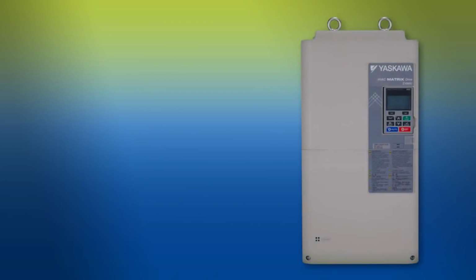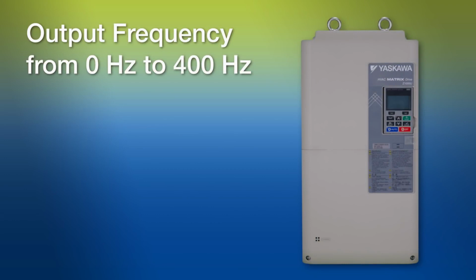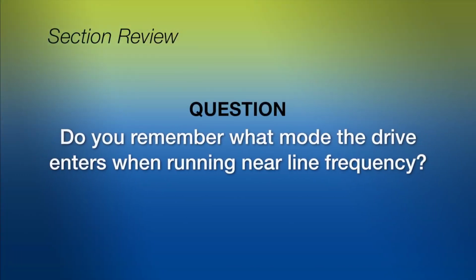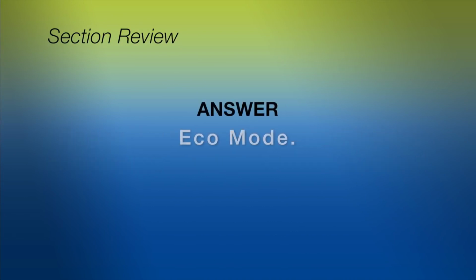The Z1000U will work for a wide variety of applications, as the output frequency to the motor can be varied from 0 Hz up to 400 Hz. Well, before we move on, do you remember what mode the drive enters when running near line frequency? That's right, the answer is eco mode. Well done.